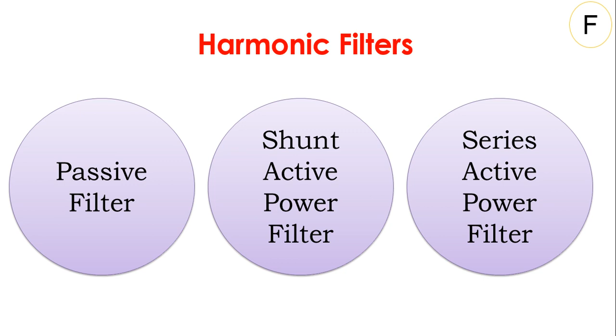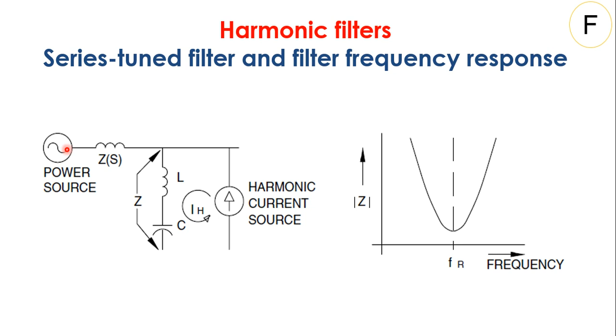Active filters are also used for improvement in harmonic mitigation, and the problem of voltage regulation can be compensated by exchanging reactive power with the system. Another series connected device is the series active power filter. These are the harmonic current source, and we can design L and C such that at the resonant frequency the impedance will be minimum, and that harmonic current will be sinking into this circuit, and your supply will be sinusoidal. This is also known as a series tuned circuit, and this is the filter frequency response.